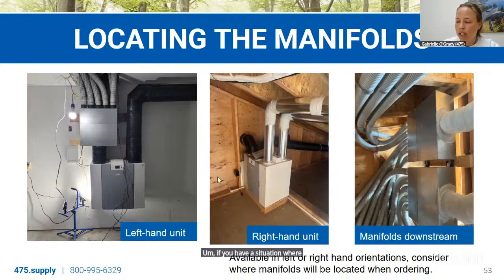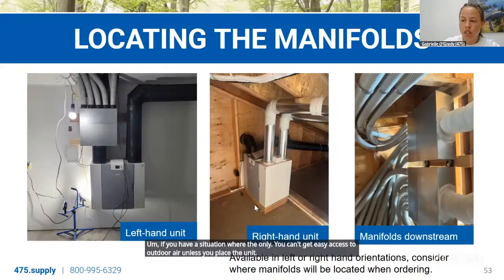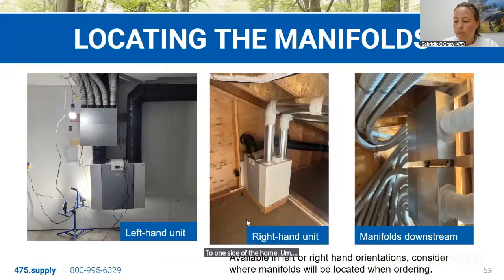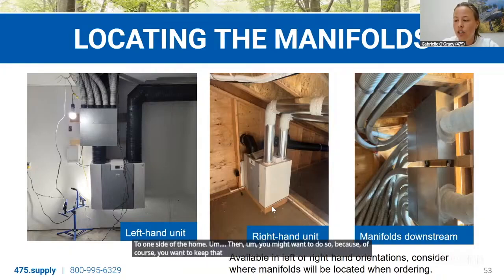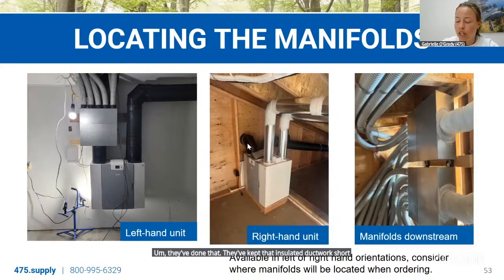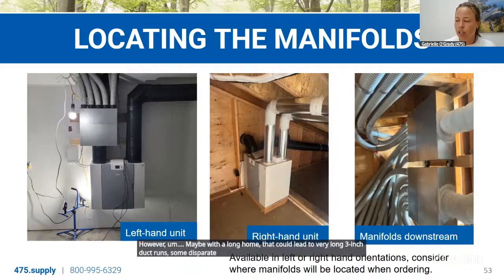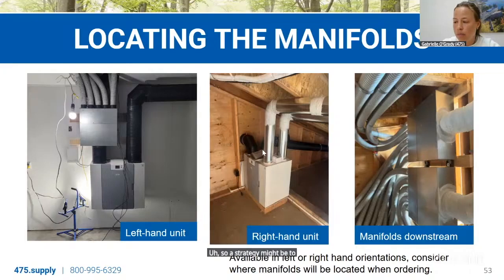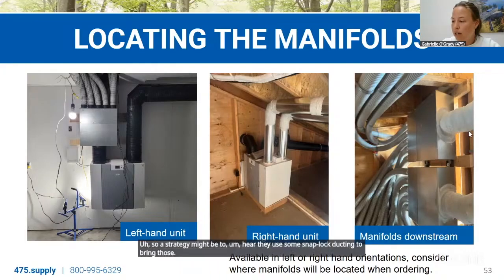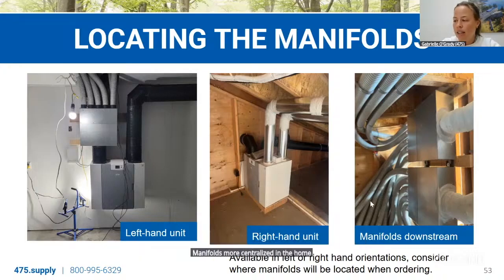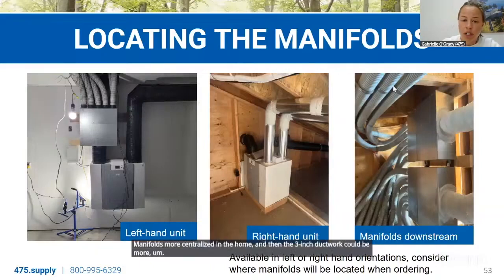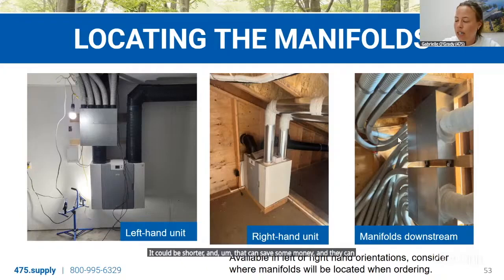If you have a situation where you can't get easy access to outdoor air unless you place the unit to one side of the home, then you might want to do so because, of course, you want to keep that insulated duct short. So in this middle photo, they've done that. They've kept that insulated duct work short, and that's where the freshest air possible was. However, maybe with a long home, that could lead to very long 3-inch duct runs, some disparate lengths in the duct runs. So a strategy might be to, here they use some snaplock ducting to bring those manifolds more centralized in the home, and then the 3-inch ductwork could be shorter, and that can save some money, and they can be more equal in length.